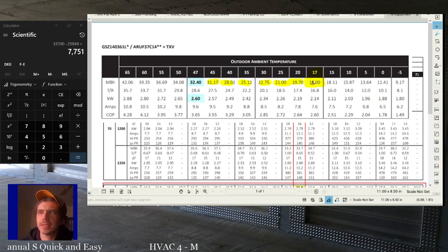The other thing is, like I said, if you're using this as your sole heat source, so you don't have backup heat, then you need to make sure that at your design temperature, so for us that's 17 degrees, you can put out enough heat.